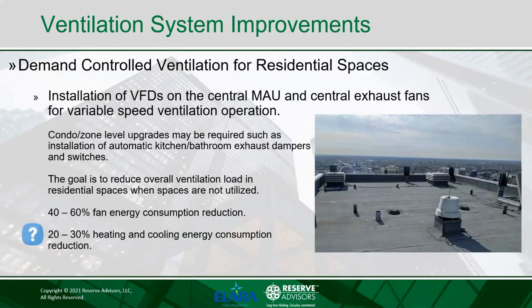So the next topic I'd like to talk about under ventilation systems improvement is also a very important one. It's demand control ventilation for residential spaces. For residential spaces, another ventilation system upgrade that can significantly reduce energy consumption is implementation of demand control ventilation. As I mentioned earlier, typically exhaust is provided by central kitchen, dryer, and toilet exhaust fans, while fresh air is provided by central makeup air units. Typically these systems operate at constant speed, regardless of the building's real-time ventilation needs. By installing variable frequency drives and upgrading controls associated with these systems, the goal here is to minimize overall ventilation load in residential spaces when certain spaces are not utilized.